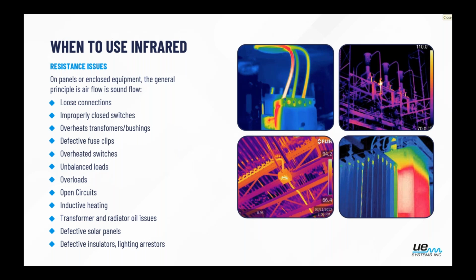And then a new one that's getting a lot of popularity is solar panels, being able to see issues with that. And then one that I don't think is done quite often enough, but is a huge benefit, is looking at defective insulators and lightning arresters. Hopefully you will never really need to have a lightning arrester do its job, but you definitely want to make sure that it actually is doing what it should.